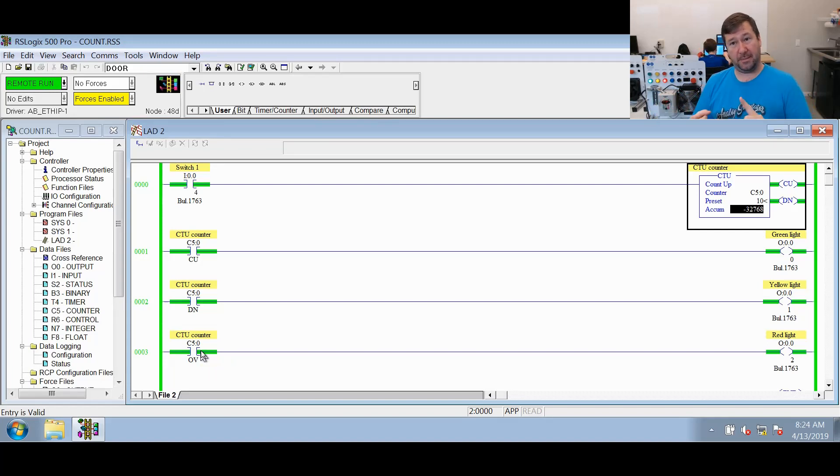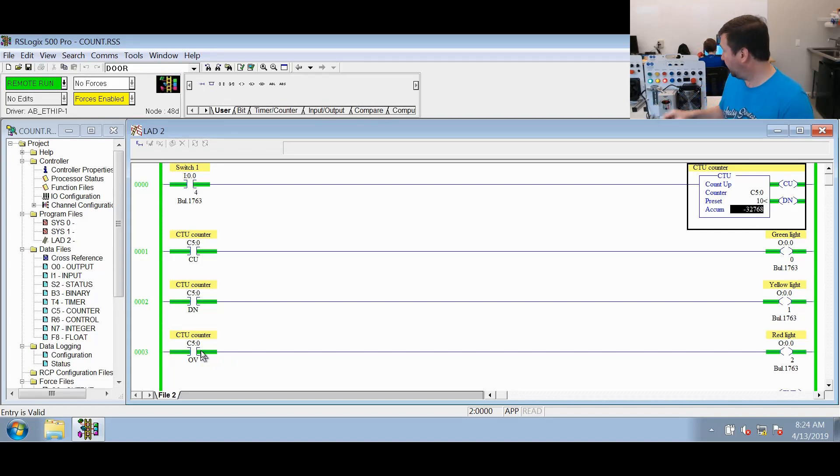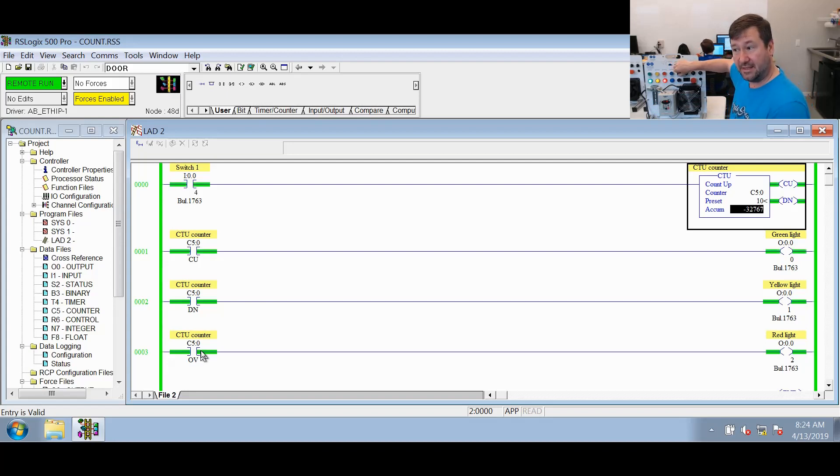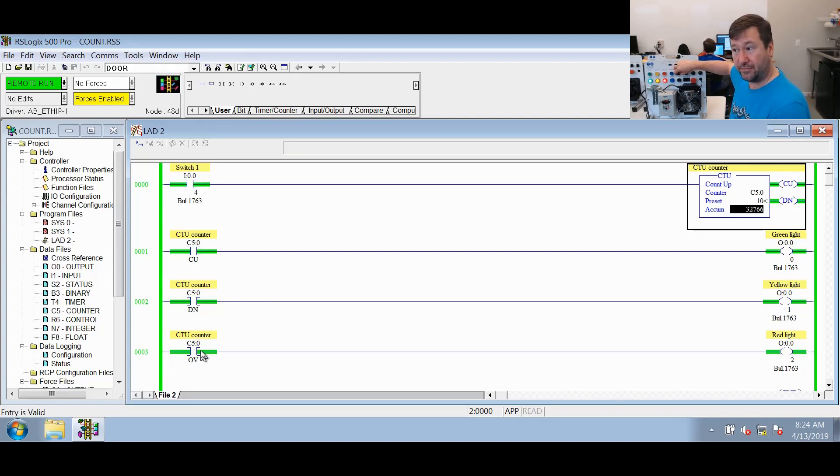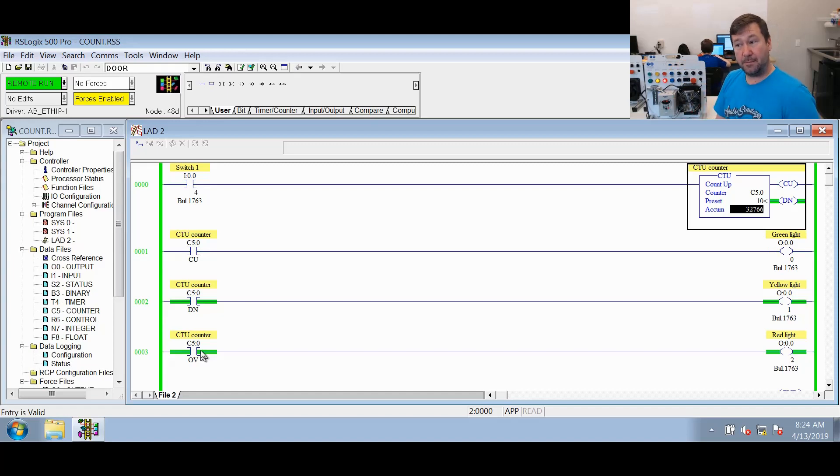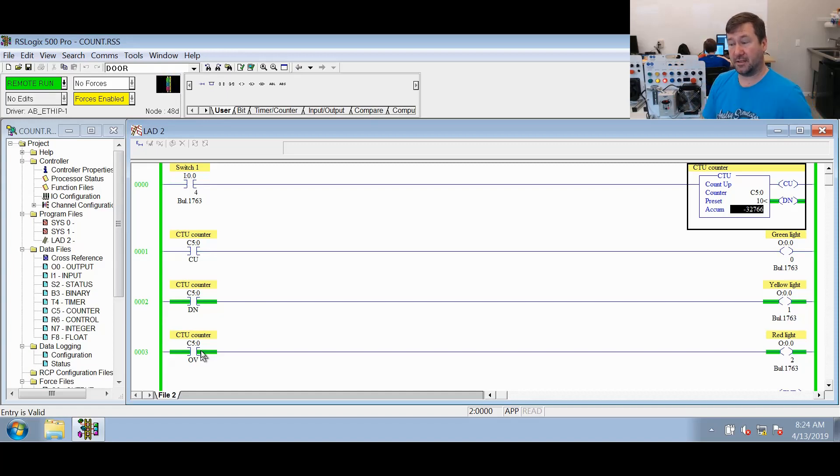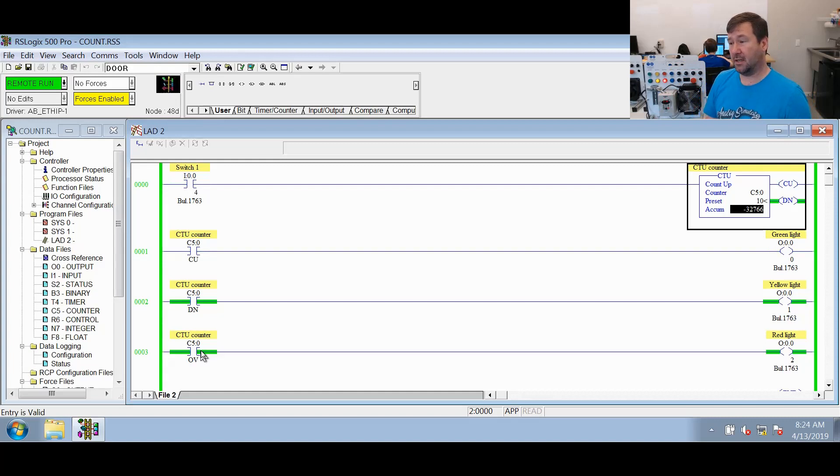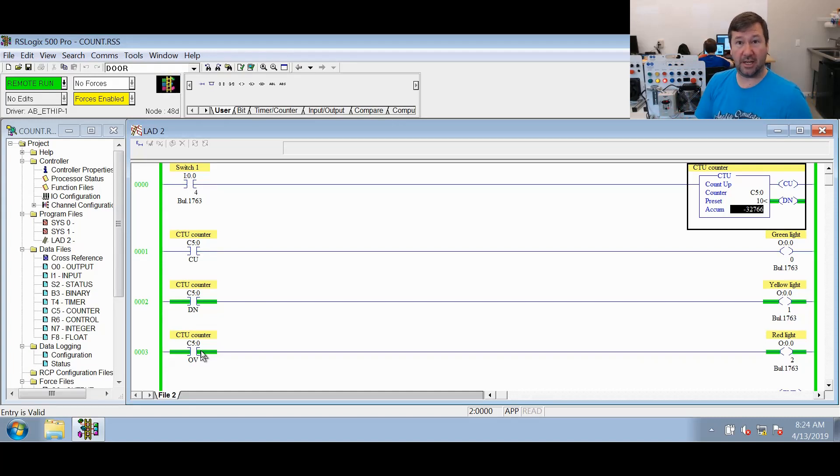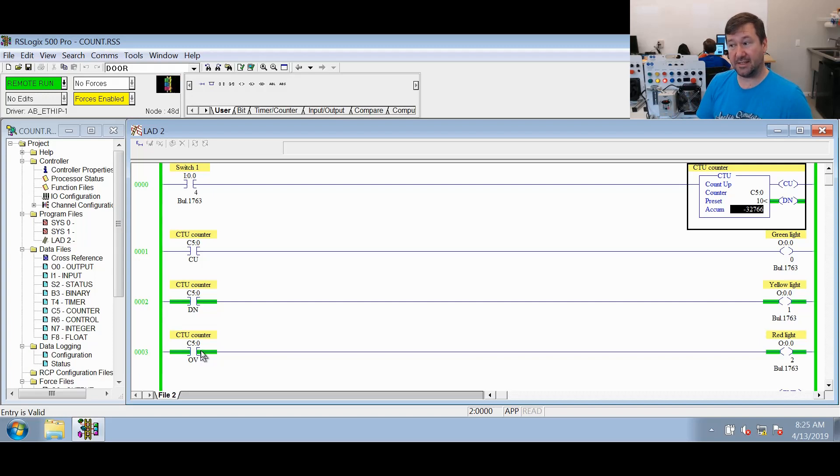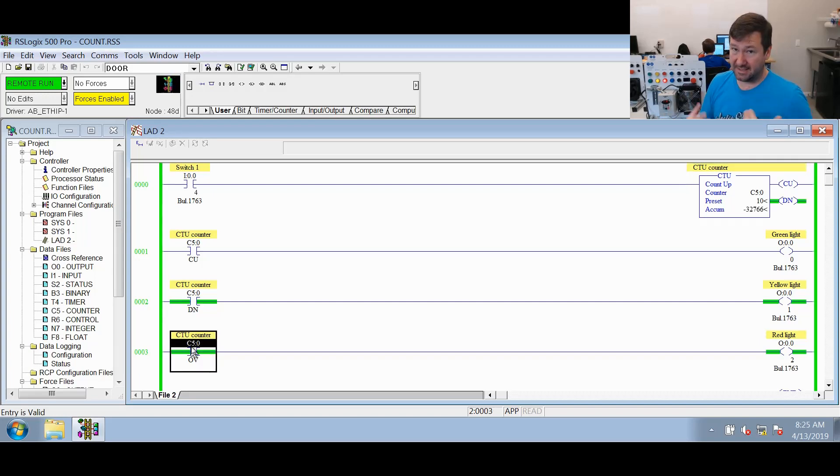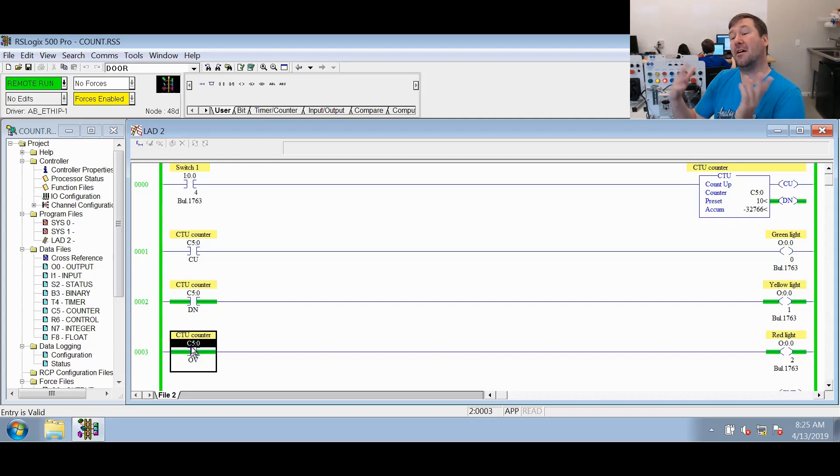The big takeaway is the count up enable bit means that the CTU instruction is true. The done bit means that the accumulated value is greater than or equal to the preset. But right now our accumulated is much less than our preset, and that's what this overflow is doing right now: it's signifying that it has counted past that.